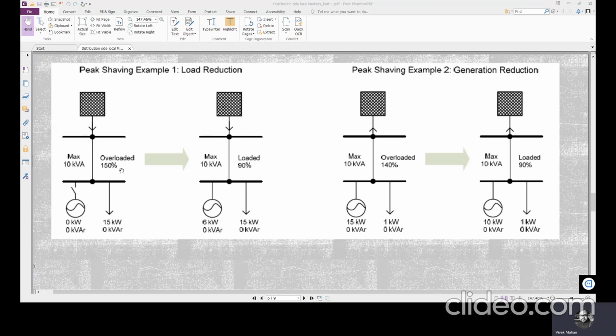Earlier it was 150% loaded, right? So when looking from the upstream grid side, the effective load has reduced, because the effective load is now 15 minus 6, which is 9 kilowatts when looking from the grid side. Earlier it was 15 minus 0, which is 15 itself, right?